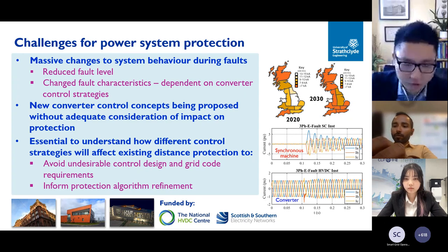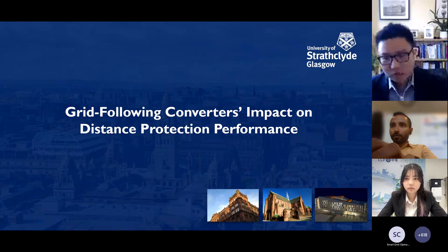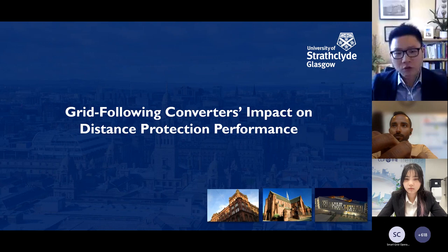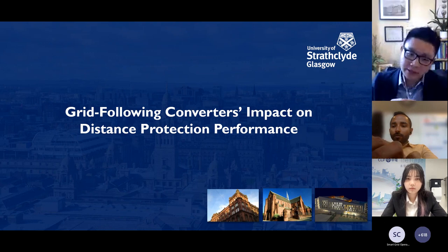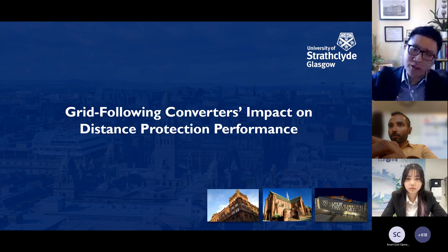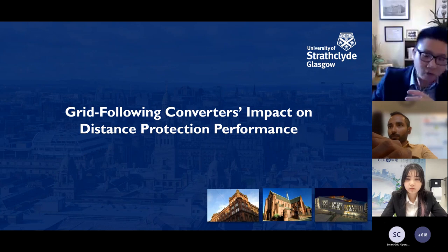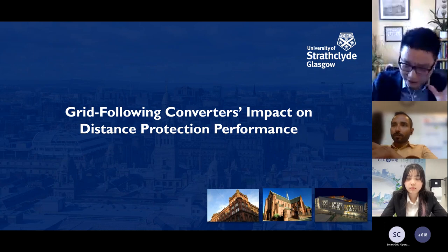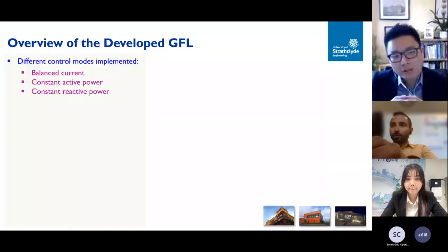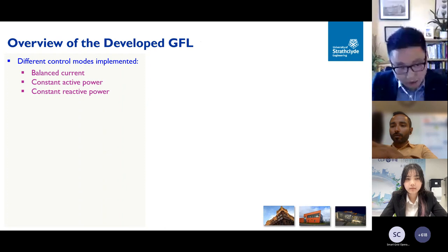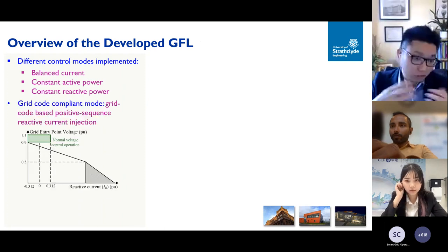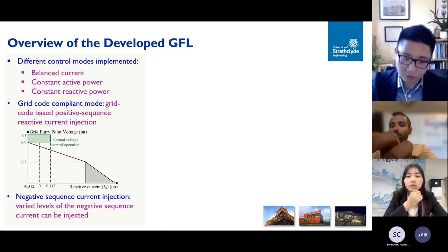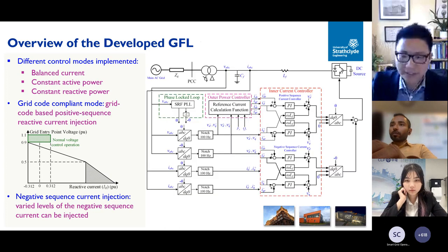to mitigate those risks. So the vast majority of wind turbines, HVDC converters and energy storage use so-called grid following control. What it means is these converters need an external grid as a reference in order for the controller to work. Okay, the vast majority of them use grid following at the moment. So what we have done is pick out typically used control strategies and prototype them in our lab, making sure they all comply with the existing grid code to make it realistic.